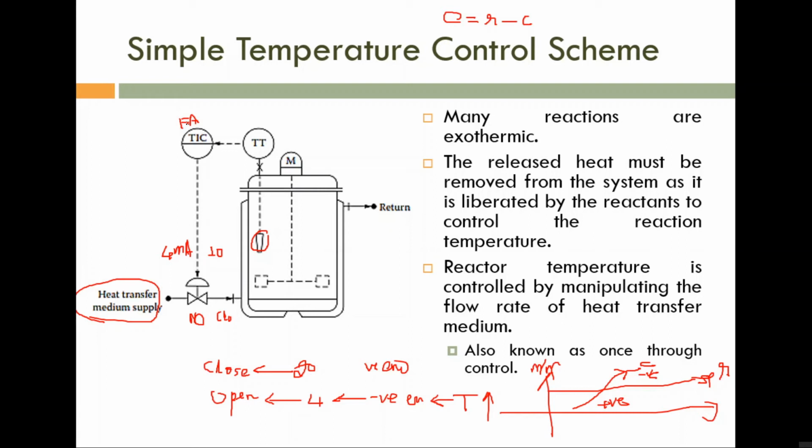Okay. So please note, first we have to know the process. After knowing the process, we have to select the control valve. Then after selecting the control valve, we need to fix the type of controller, whether we require forward acting or reverse acting. Now, control mode. What type of control mode do we have? Discontinuous or continuous? Yes, exactly, because temperature variation is not allowable, a continuous controller we have to use. Good answer. Next one, proportional control mode or PI control mode or PID control mode.